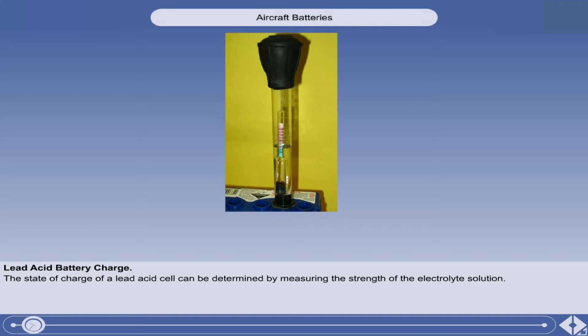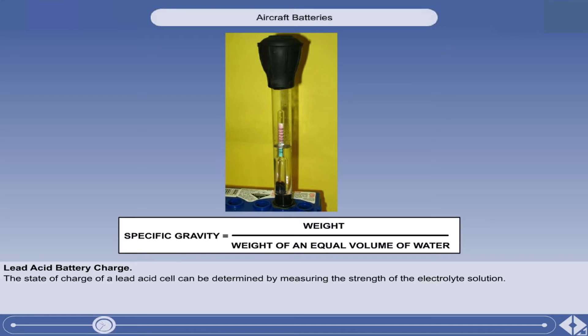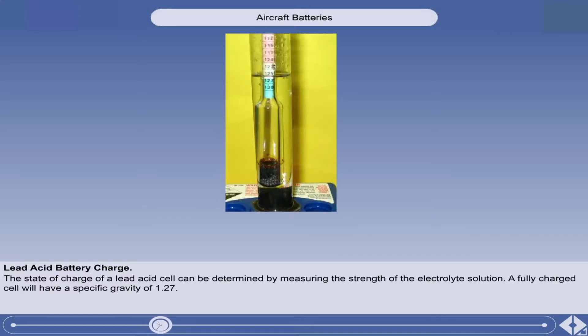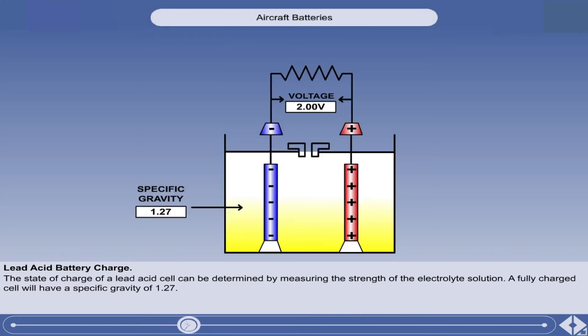The state of charge of a lead acid cell can be determined by measuring the strength of the electrolyte solution. This is done with a hydrometer, which measures the specific gravity. The specific gravity of a liquid is defined as its weight divided by the weight of an equal volume of water. A fully charged cell will have a specific gravity of 1.27. When the cell is connected to an external circuit and current is flowing, the acid becomes weaker and its specific gravity falls.